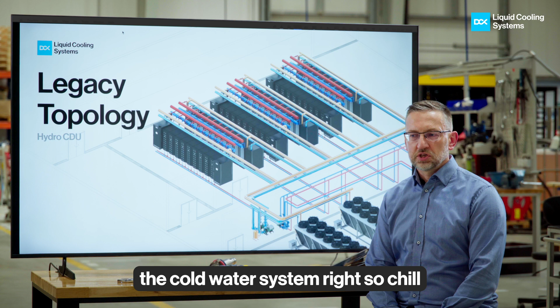And that's where the troubles start - that's when we become worried about the space. So what we suggest is to change the idea. Don't look into the generic topology number 300-whatever from those major vendors. They are experts in the field of electricity and power distribution, but not in the liquid cooling space. Look outside, start with experts.